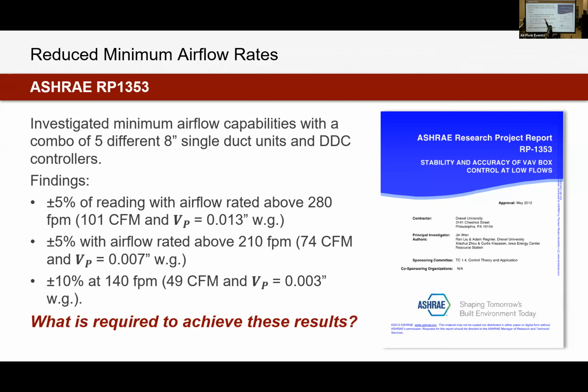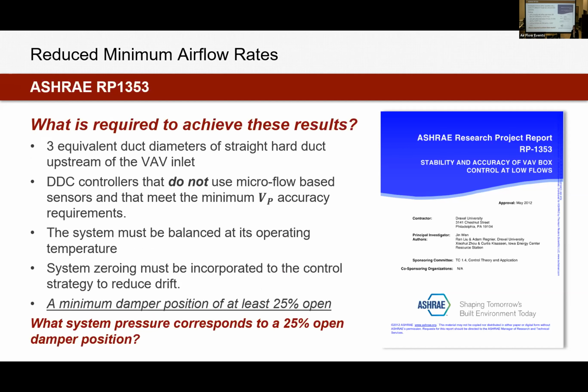Look at the velocity pressure here. All manufacturers catalog down to 0.02 inches. So you can see how low we're getting on the velocity pressure, all the way down to 0.003. Really small velocity pressure across that sensor. ASHRAE concluded that you can get those readings down to plus or minus 5%, you're still getting an accuracy of plus or minus 5% by turning down below recommendations. Sounds a little bit too good to be true, and it kind of is. There's a lot of caveats that resulted in these findings.